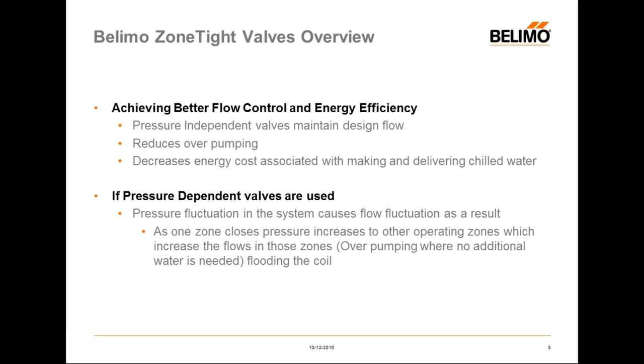A ZoneTight valve — we try to achieve better flow control and efficiency by using a higher quality valve. We use a pressure-independent valve, which maintains design flow. It reduces over-pumping and decreases the energy costs associated with making and delivering chilled water. If pressure-dependent valves are used, pressure fluctuations in the system will cause flow fluctuations as a result.